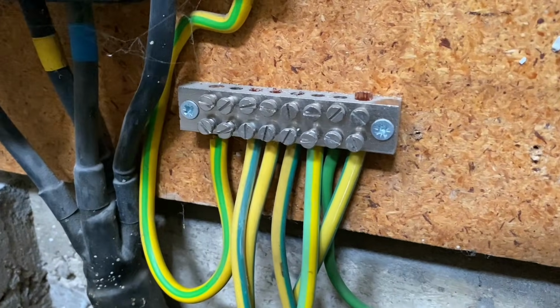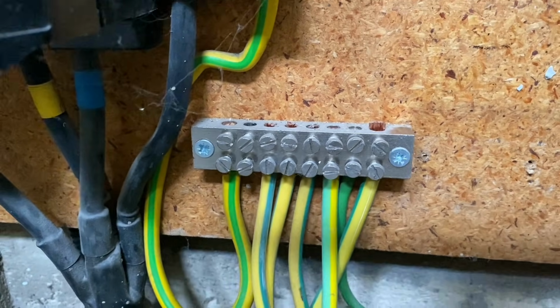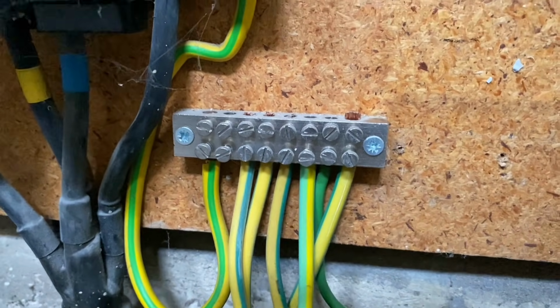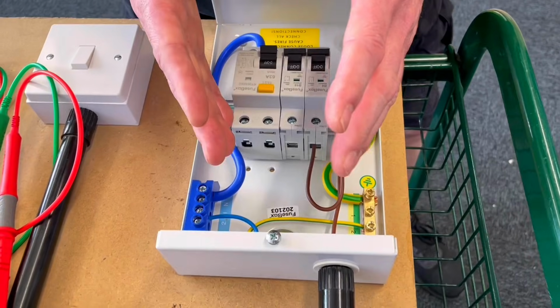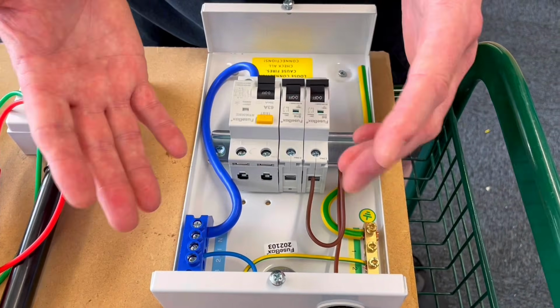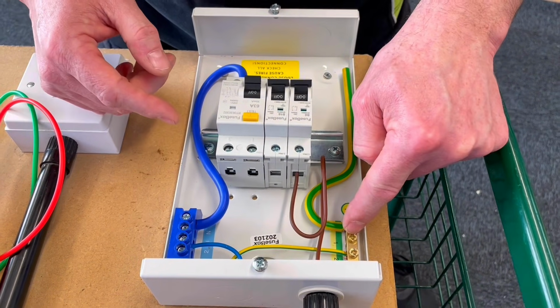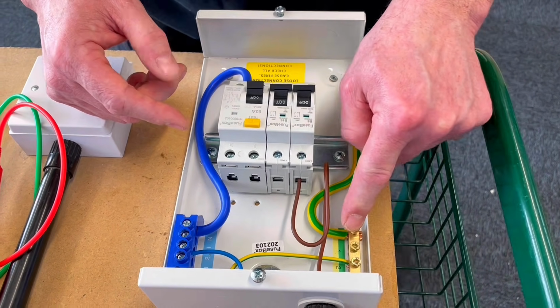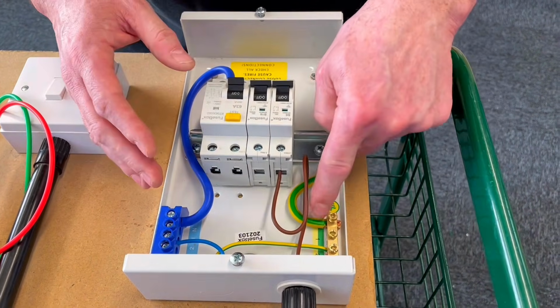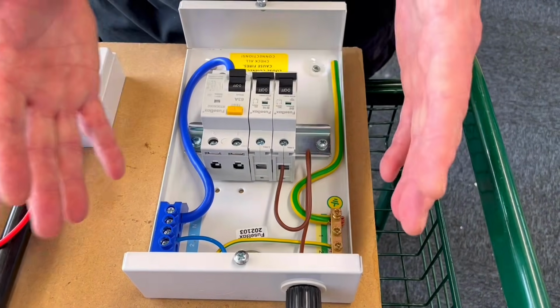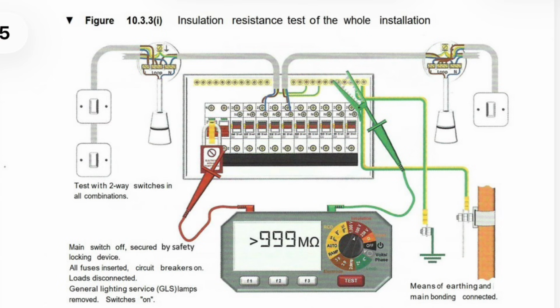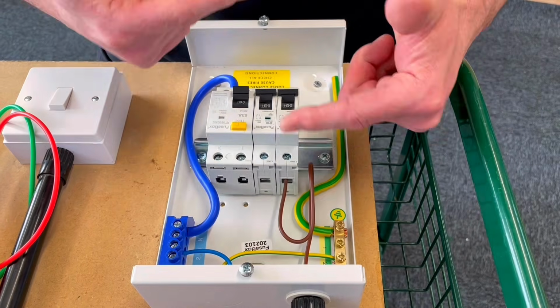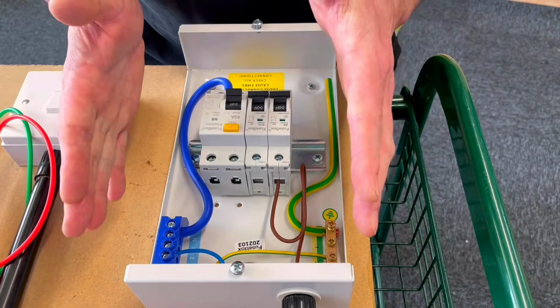If there was an earthing terminal, an MET, this green and yellow earthing conductor would go there, and the bonding must be in place. So if the circuit has bonding to gas, water, oil, etc., all of the bonding conductors must be connected in this earth bar as well. I know at college that's probably not going to be the case, and you're not going to have these in place because obviously it's not connected to the electrical system. But the sooner you hear the fact that when you carry out your insulation resistance test, the earthing conductor and bonding conductors must be in place and connected, it helps you to move through your levels of understanding and knowledge.